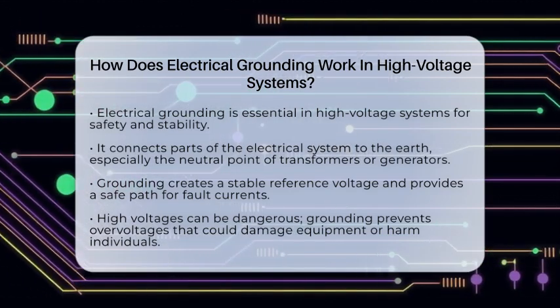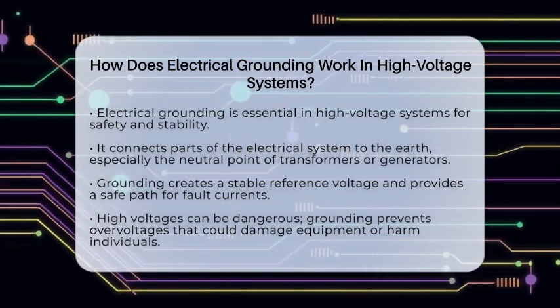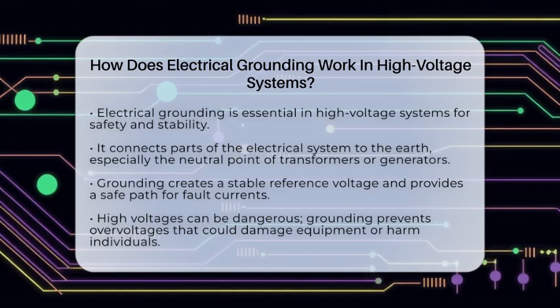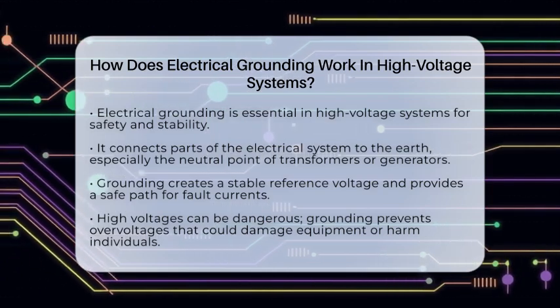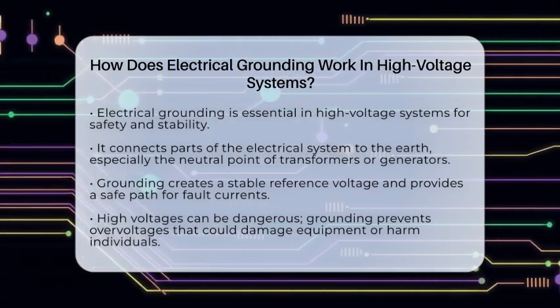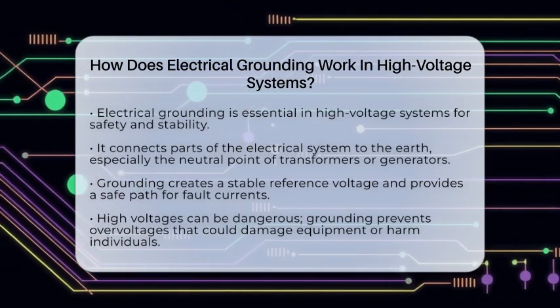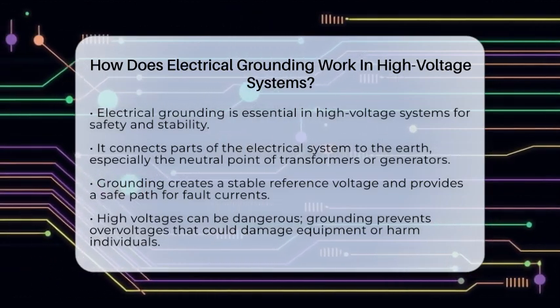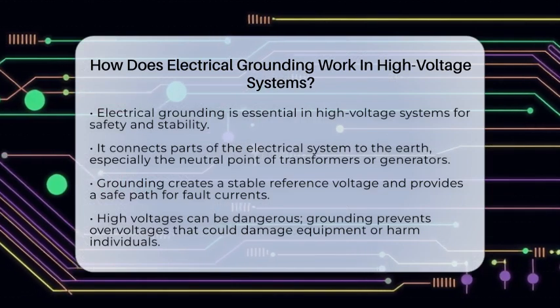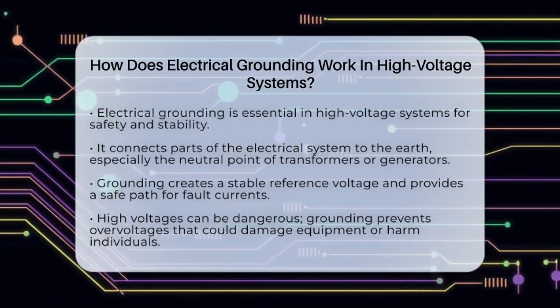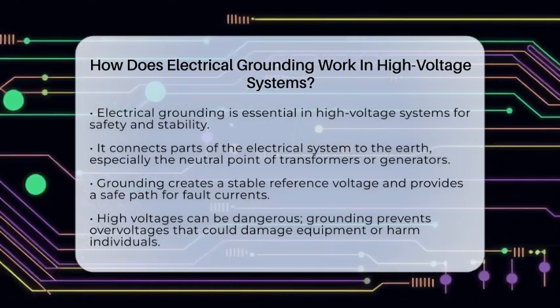In high-voltage systems, grounding is critical. High voltages can lead to dangerous situations if not managed correctly. Grounding creates a low-resistance path between the electrical system and the earth. This is essential for preventing overvoltages that could damage equipment or harm individuals.